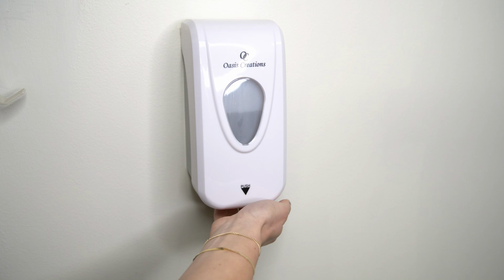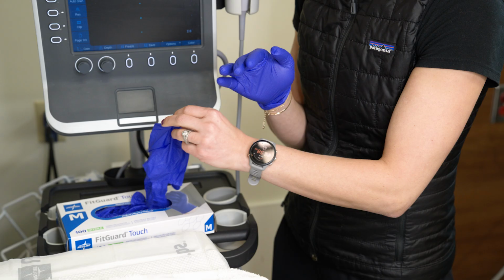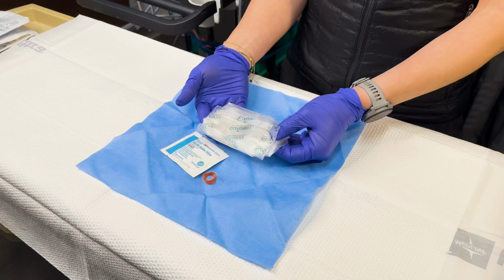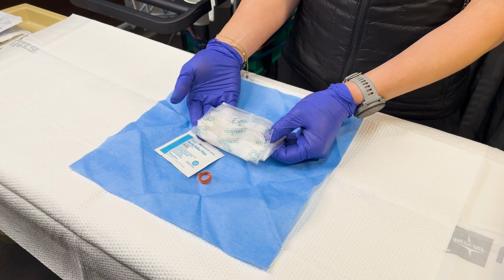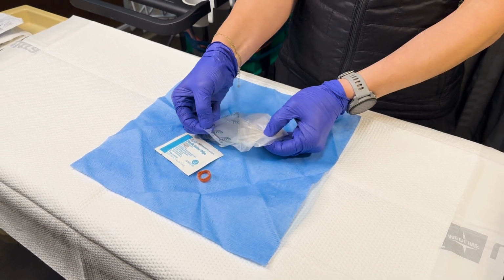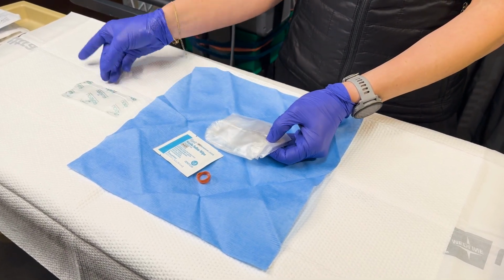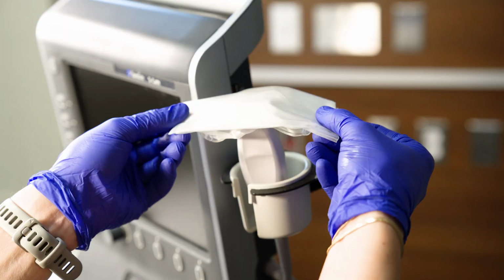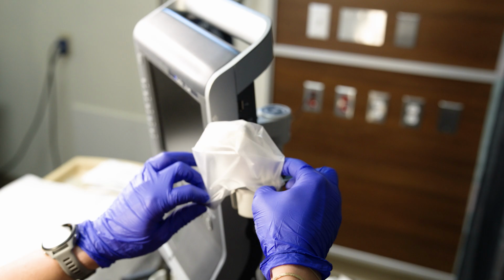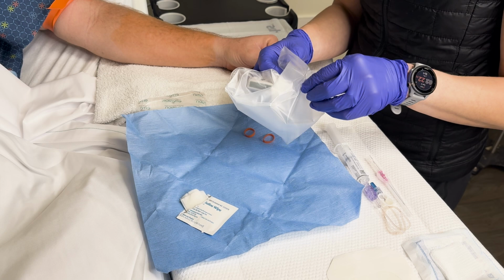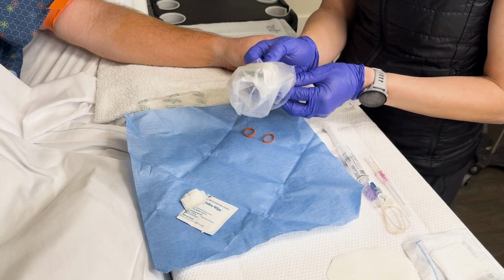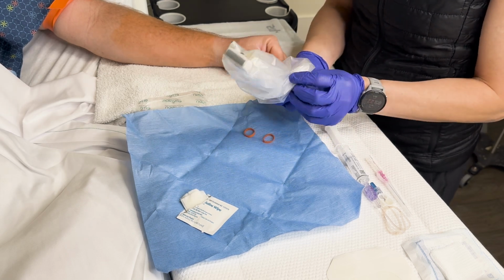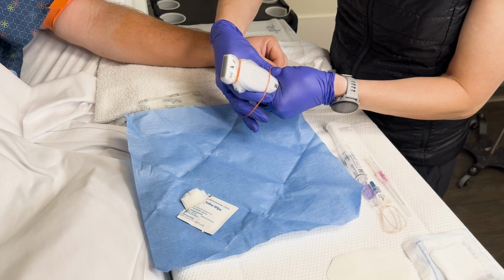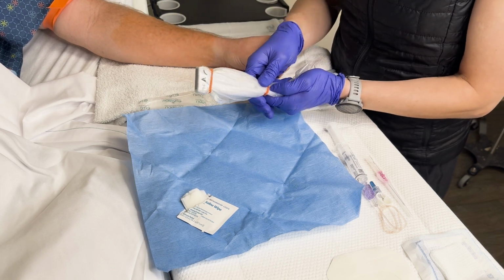Start by disinfecting your hands and donning gloves. Open the Envision probe cover, being careful not to compromise asepsis. Peel the liner away from the cover to expose the adhesive pad. Place it onto the face of the probe and pull the cover over the probe, ensuring the key part of the cover that contacts the patient's skin is not touched. Secure the cover with the enclosed bands.